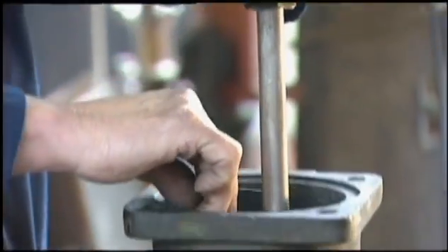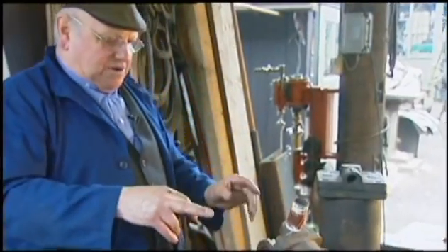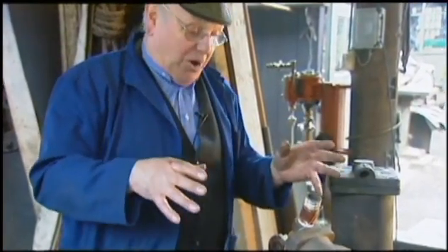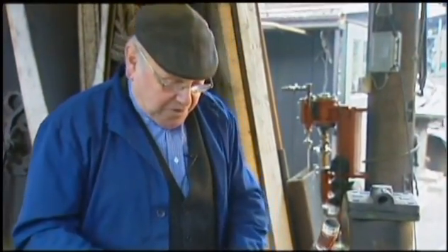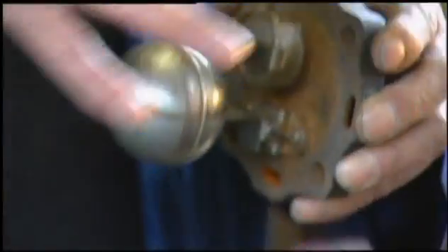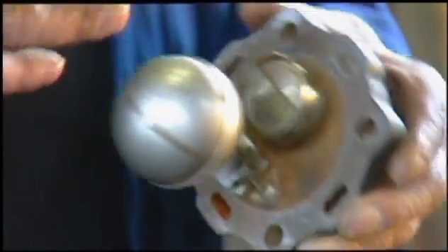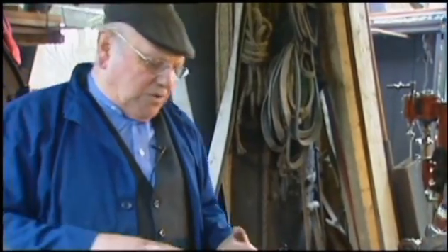It's the mechanisms in most steam traps that cause problems for steam users. These are interesting because they're like your cistern on your toilet — it's like a ball cock operation. There's the ball, but there are so many mechanical bits, and they all got rusted up. When you pull them apart they were all full of mud and looked rather horrible.